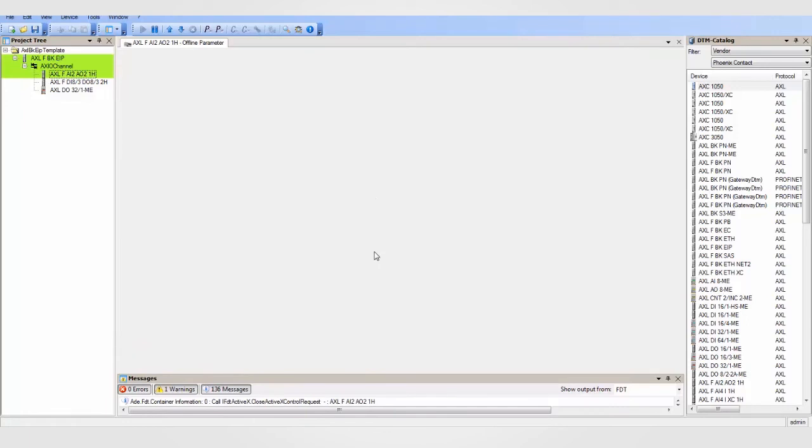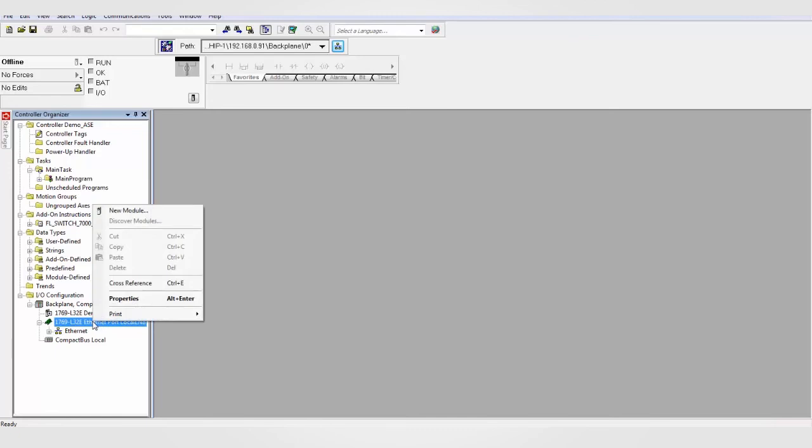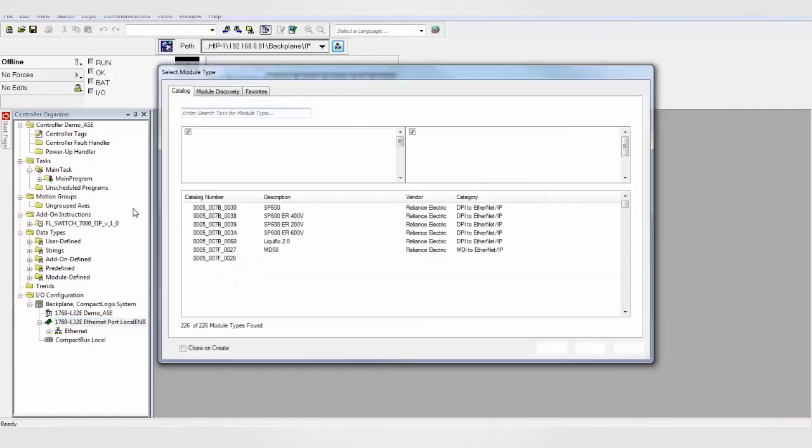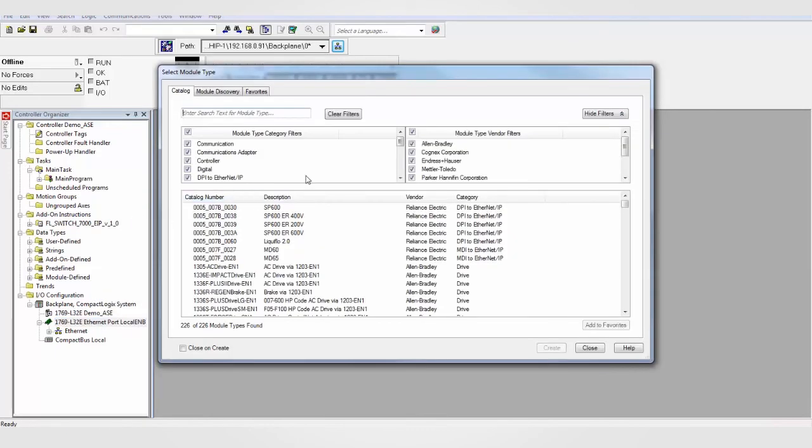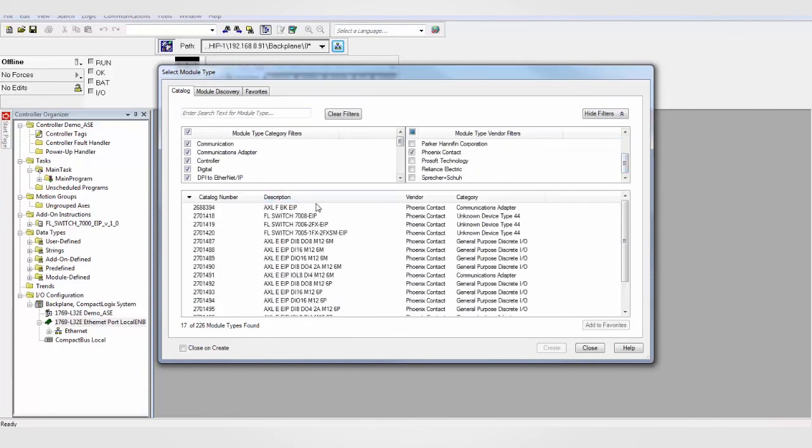Now the station is configured and we can insert this device into your RSLogix 5000 project. Simply right-click on the Ethernet port in your controller configuration and select New Module. In the Select Module Type window, uncheck the Module Type Vendor filter and then select Phoenix Contact as your vendor type. Now you will see a list of available Phoenix Contact devices.